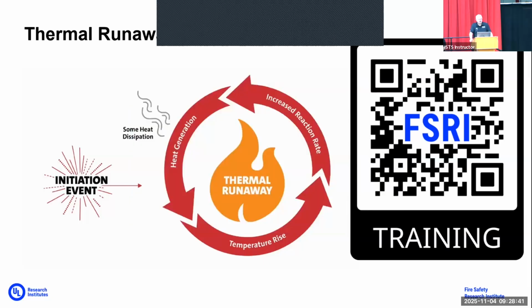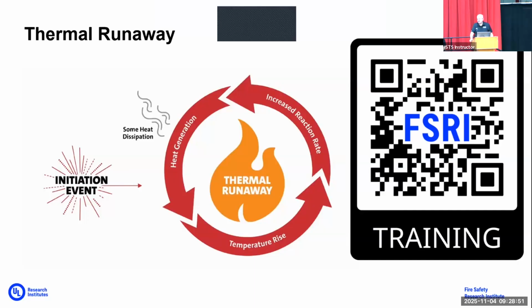So as electricity is either put into the battery or taken out of the battery, there's going to be a temperature rise within the battery. And if the flow of energy increases, that temperature rise is going to increase. In turn, that increased temperature is going to cause the chemical reaction to go even faster. That's why these batteries typically need to be used with a battery management system.